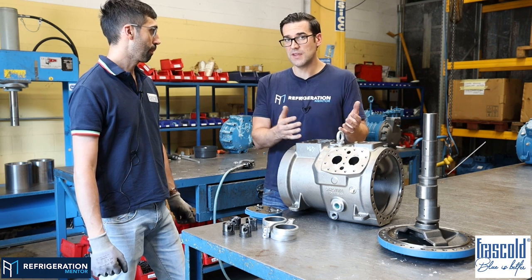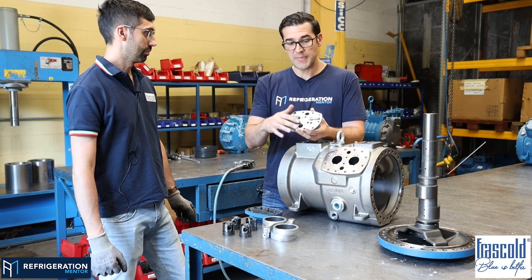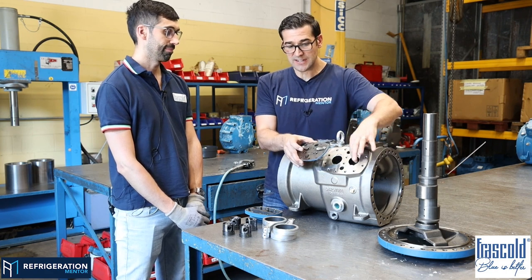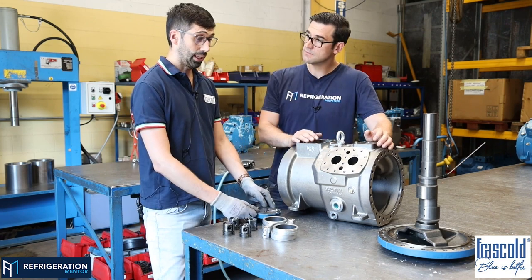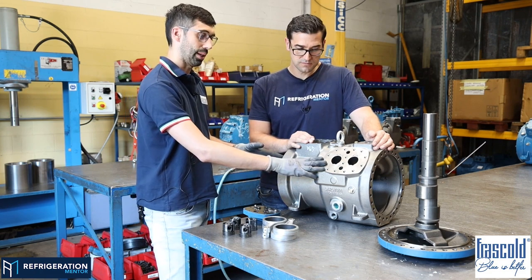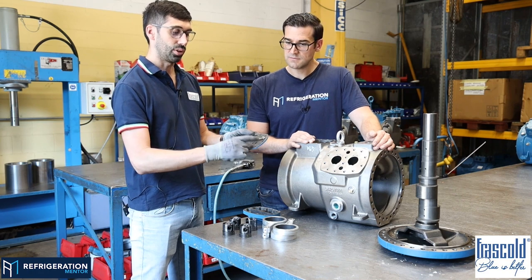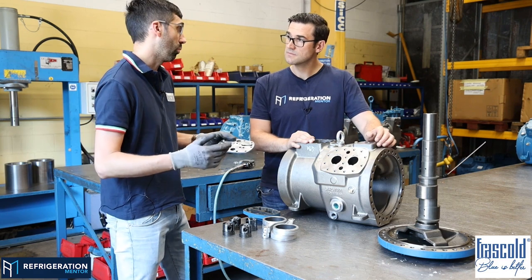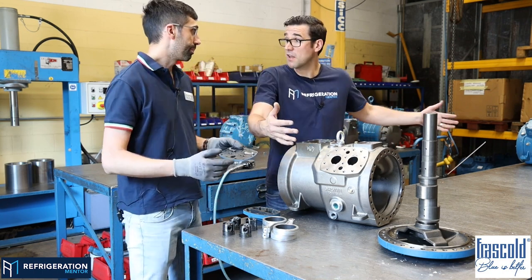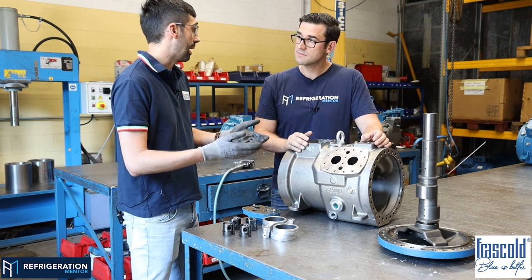So fantastic. So that's a few things, right? If you do get a situation where you break this, could be from a potential slug, could be from thermal stress that breaks this, what about while this is on there? Just say it's a long period of time that this is broken. Now I know that I got discharge gas pushing down onto the piston. What could that do? As usual, the soonest you detect a problem, the better the mechanical situation of the entire compressor. If the damage was prolonged and you, for example, lost just one piston and all the three other pistons are working well, maybe you cannot immediately understand that your cooling capacity is reduced by one quarter. Well, if you're on a parallel rack, you could have six compressors, right? In all situations, easy to detect. Yes. But if you don't detect in a reasonable time, what happens?